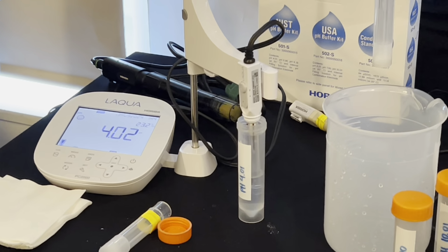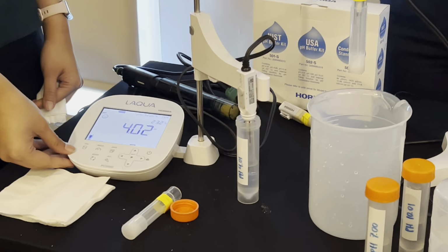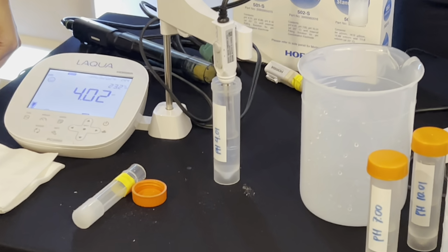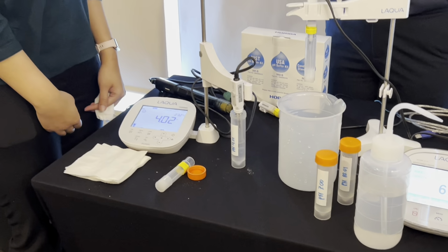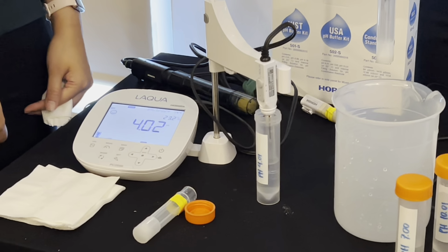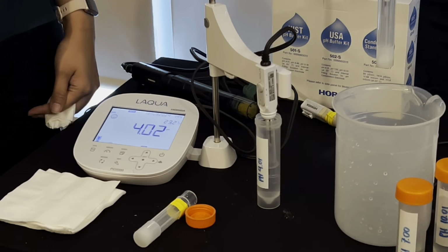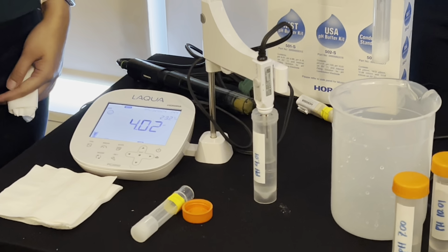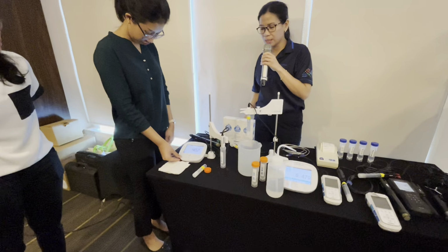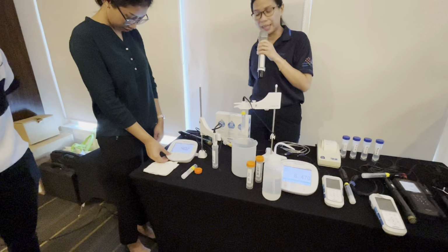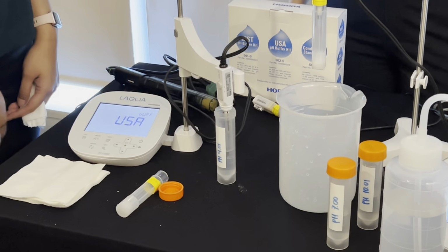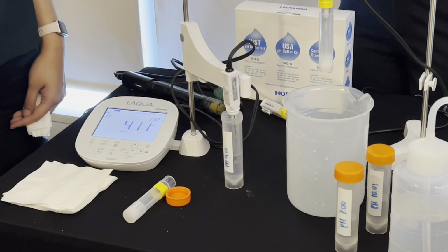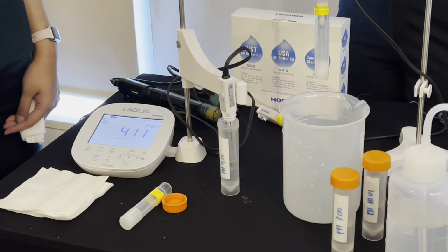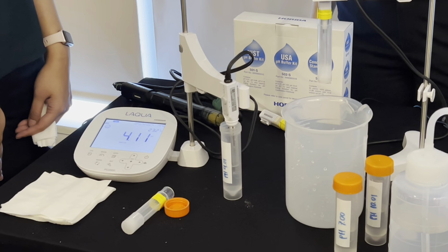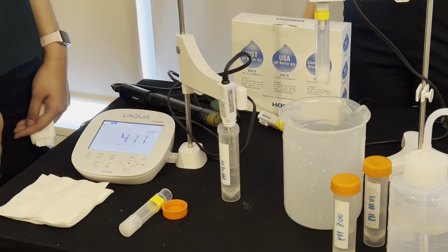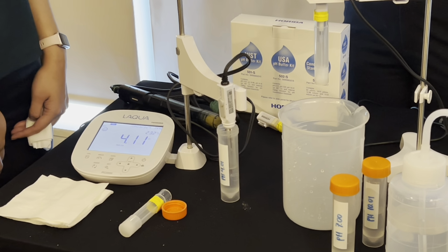Okay, so now we have immersed our electrode in pH 4 buffer. Yeah, so it already signaled that it's stable, right? And then there's also the smiley. So now we can proceed with the calibration since the reading is stable by pressing cal again, right? If you notice, after completing each calibration, it went back to measurement mode, right? So now it's reading the buffer.